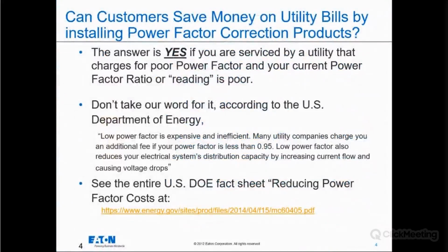So, can customers save money on utility bills by installing power factor correction products? The quick answer is absolutely yes, if you are serviced by a utility that charges for poor power factor and your current power factor readings are low or poor. But don't take Eaton's word for it. You can look at the Department of Energy's website to find where they state low power factor is expensive and inefficient. Many utilities charge you an additional fee if your power factor is less than 0.95.